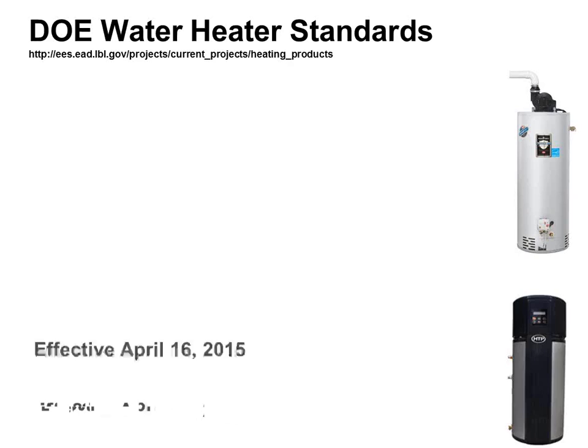On the electric side, if it's a small one, below 55 gallons, you can continue to have electric resistance-based heat if you wish. On the bigger ones, above 55 gallons, you have to have an energy factor of 2 point something, right? Once I get above 100% efficient, which would be a 1.0 energy factor, the only thing I can do is heat pump technology.